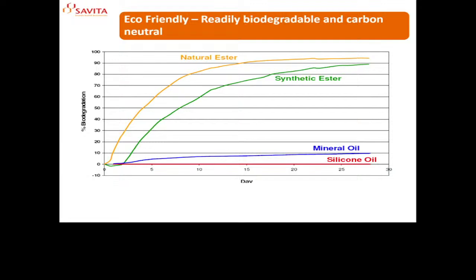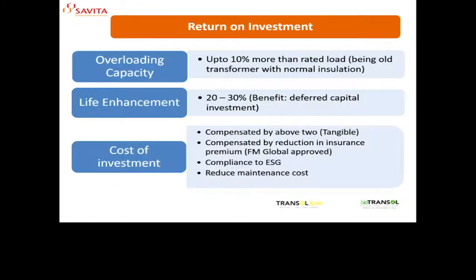Of course, ester oils, natural and synthetic, are both eco-friendly. They are readily biodegradable, whereas mineral oil is based on hydrocarbons and is not biodegradable. So any leakage or seepage into water, or any leakage on the soil, will cause permanent damage and disaster. But in the case of ester fluids, there is absolutely no worry.